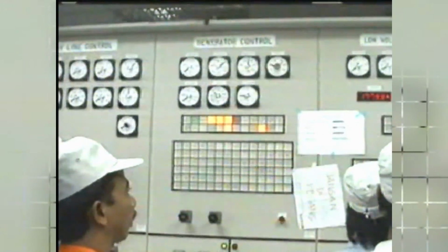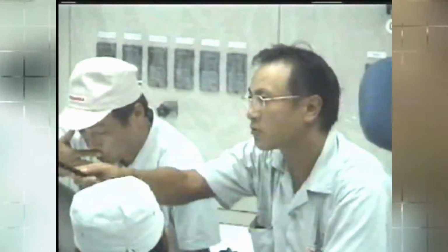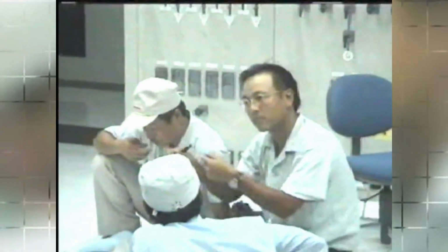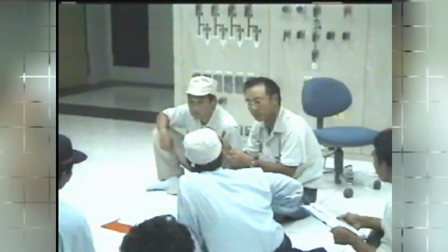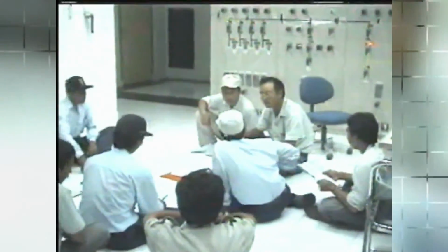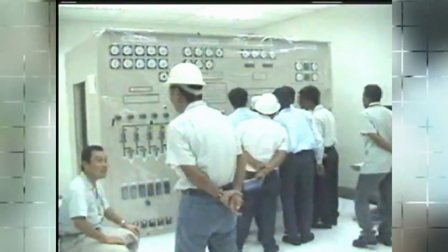The generating equipment is subject to the reliability test to operate at rated speed, normal voltage, and outputs within the specified limits under the operating conditions of the station, either continuously or intermittently, without failure and undue interruption of any kind resulting from defect of the plant for a period of 500 hours before taking over.